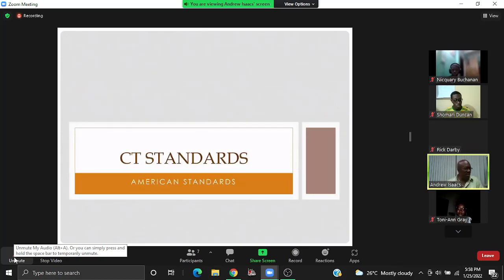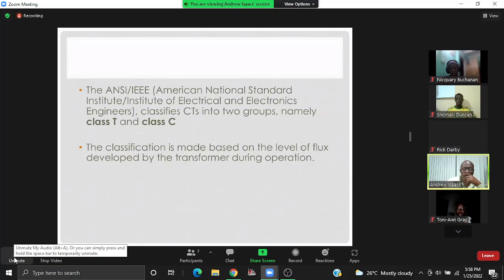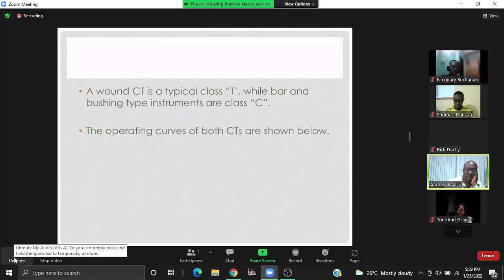So, we now come to the American standard. But I will pause if you have any questions out there. No? All right. So, your CT, your American standard, the ANSI/IEEE, yes? We have two groups. We have the class T and the class C. And I'll tell you that most of our work will be focused on the class C CT. A wound CT is typically a class T, while the bar or bushing type are class C.